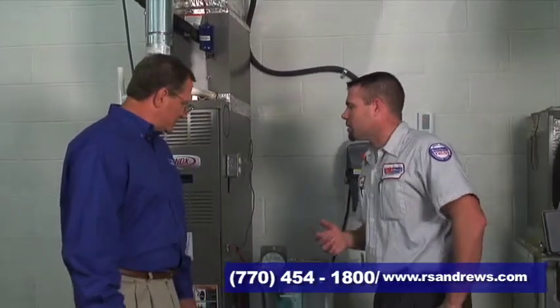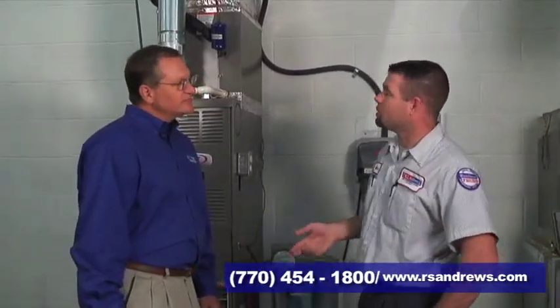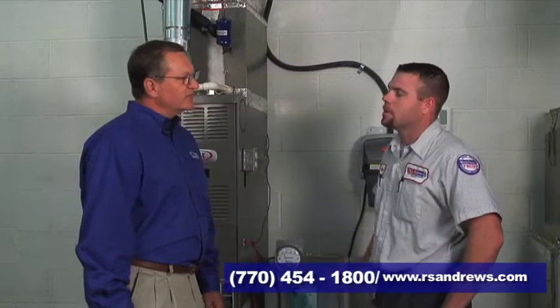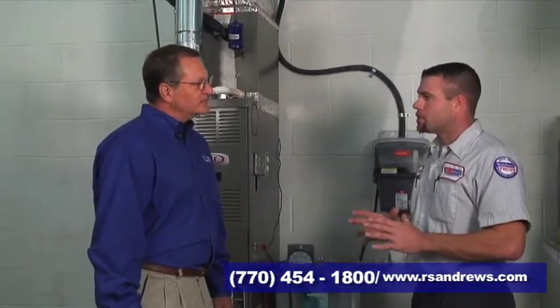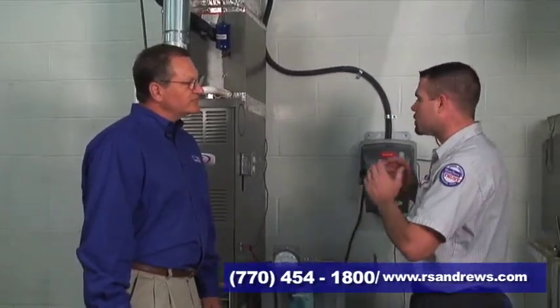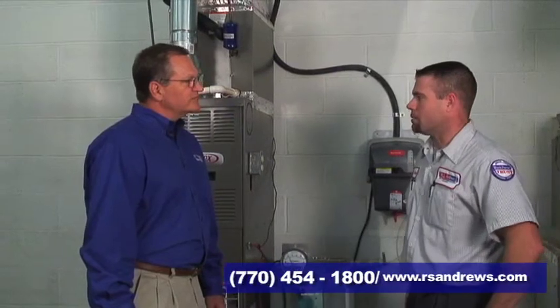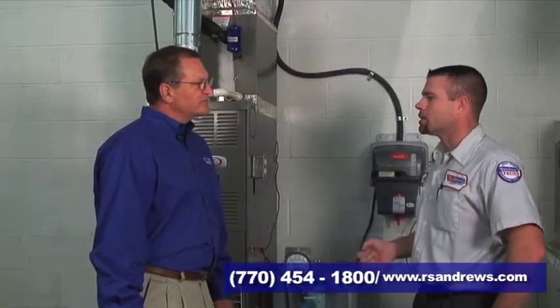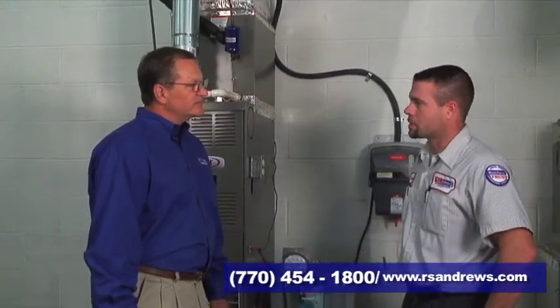Static pressure is basically how hard the blower motor has to work to move air through your duct system inside of your home. We have to look for certain numbers of static pressure in order to ensure the equipment is actually working right. Make sure the blower motor is not working too hard and you're getting the air delivered to your home like it's supposed to.